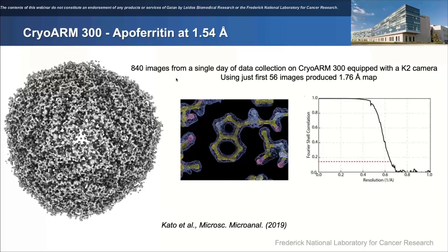When we saw this result, we got even more excited about what we could do with the cryo-arm 200. One thing we took notice of was that when they analyzed the data set, they noticed a changing beam tilt over time during data collection. They eventually determined that each time the objective lens setting was changed, there was a change in beam tilt. With apoferritin's high symmetry, you could potentially overcome imperfect beam tilt estimation by sheer numbers and high particle density. But for other samples this would not be possible, so we had to find a way to work around this more robustly.